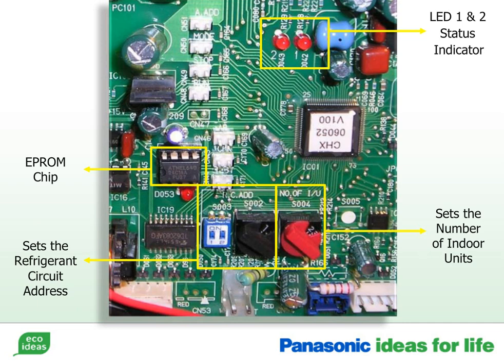The EEPROM chip is a non-volatile and removable configuration storage device. Indoor and outdoor unit information is written to and stored in this chip. The pins labeled A.ADD, CN51, are used to initiate the auto-address procedure. When the auto-address is in progress, the outdoor unit looks for all the indoor units connected to the SNet, and communicates with them. Once this procedure is completed, and correct, it is stored in the EEPROM chip.